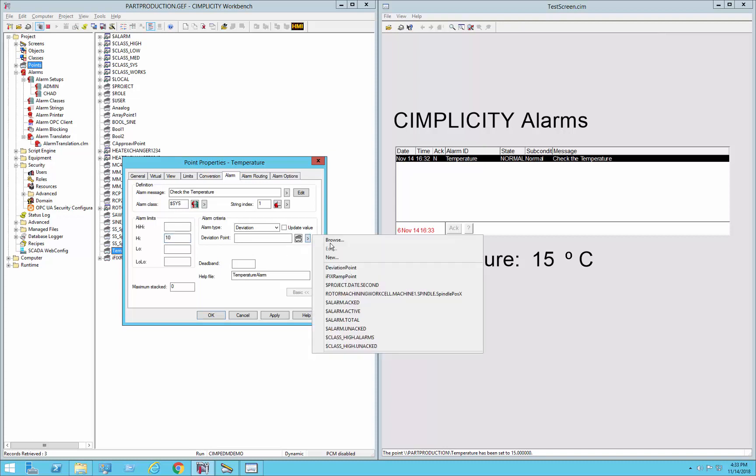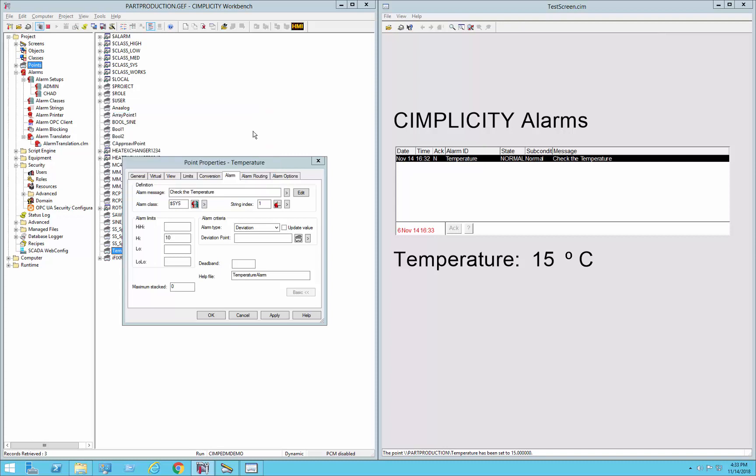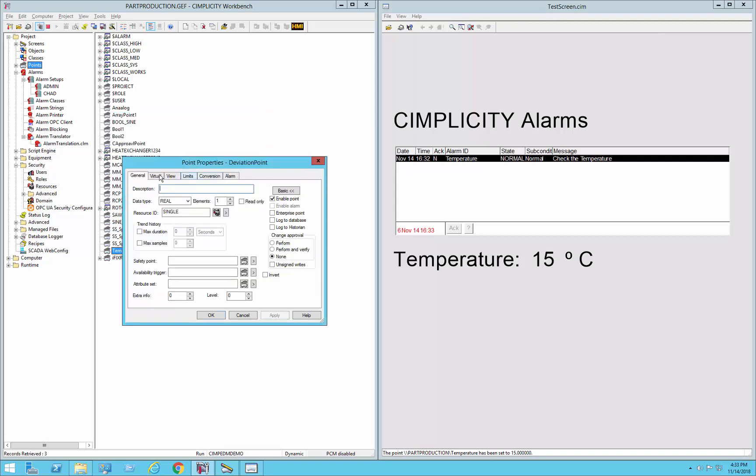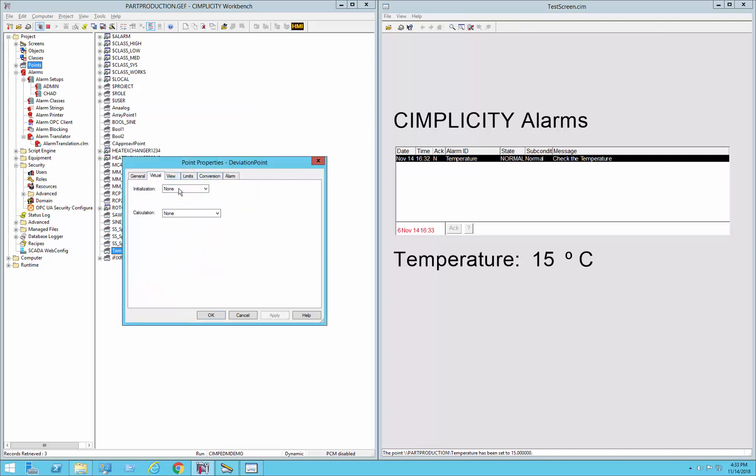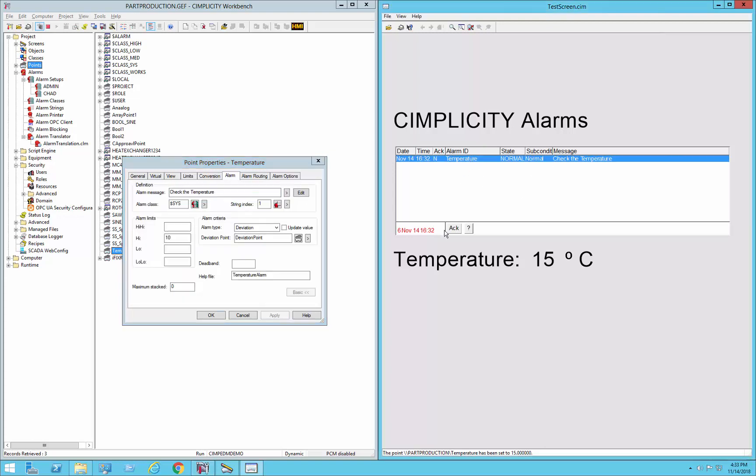So in this case, we need to specify an actual point. So we're going to create a new virtual point called the deviation point. Simple enough. And we'll say that its value will start out as, let's say, 10. So anything, the difference between the current value of our point from 10, if it's greater than 10, then it will be a deviation. So let's apply that. You can see that, acknowledge that.